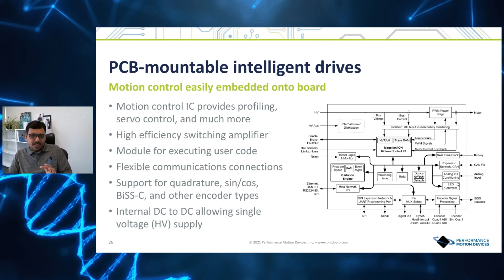The other common request we get is separating your high voltage and your HV aux, the low voltage that runs the processors, for safety reasons. That way, if you have STO or some safety feature implemented, you can shut off the high power and the motor, but the processors stay up and running and can still communicate what error conditions are observed. This is a pretty critical safety feature implemented in this drive.